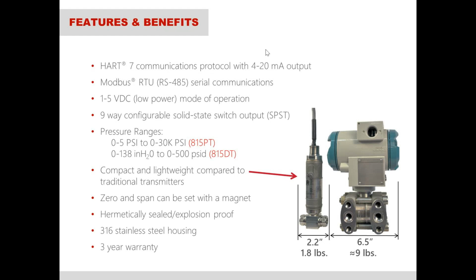communications, a 1 to 5 volt low power option, a 9-way configurable switch, and then also it has external magnetic zero and span targets to adjust it externally with magnets. All of that comes inside the 815 PT whether you ask for it or not. So there's no selecting whether you want HART or Modbus or any of that stuff.